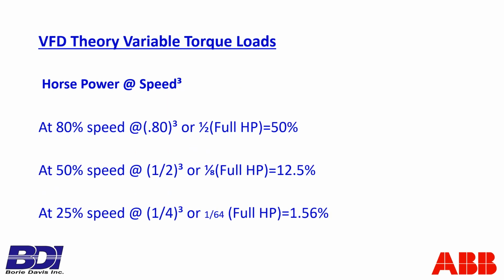So here we're just bringing together the power versus speed relationship that I've already mentioned audibly, but here it is mathematically. At 80% speed, 0.8 cubed equals 0.5 times your full horsepower, equals a 50% energy savings with still only a reduction of 20% flow. And the 50% speed and 25% speed are given there as well.